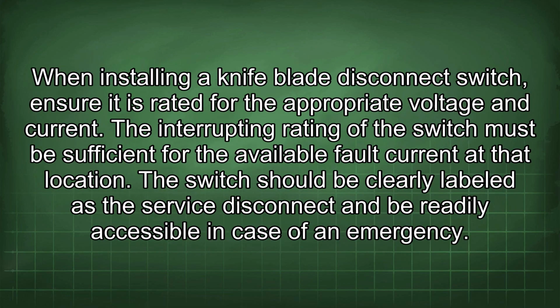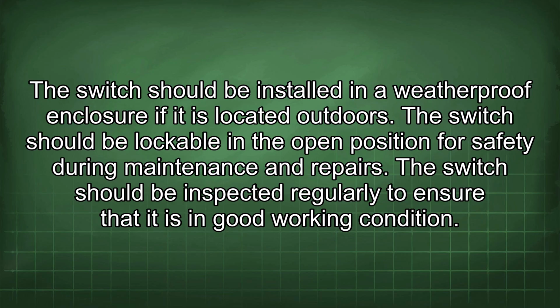When installing a knife blade disconnect switch, ensure it is rated for the appropriate voltage and current. The interrupting rating of the switch must be sufficient for the available fault current at that location. The switch should be clearly labeled as the service disconnect and be readily accessible in case of an emergency. The switch should be installed in a weatherproof enclosure if it is located outdoors. The switch should be lockable in the open position for safety during maintenance and repairs.